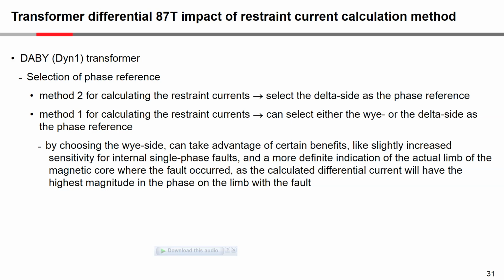And so remember that even though the relay may have operated now in 3 phases, if you had to look at a disturbance record or something like that, you would see clearly the phase that had the fault. Whereas with the delta side as the phase reference, it would operate in 2 phases. And if you looked at a disturbance record, you would see that those 2 phases would have essentially the same amount of current.